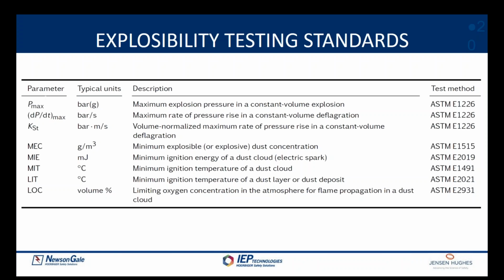Pmax and KST. KST is a term for a volume normalized maximum rate of pressure rise in a constant volume deflagration. This concept was developed in Germany, so it's not surprising that ST stands for Staub, which is German for dust. Pmax and KST are two parameters that are used both in the design of explosion suppression systems and deflagration venting. And there'll be more discussion about this later in this webinar.